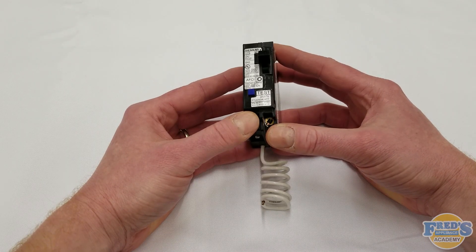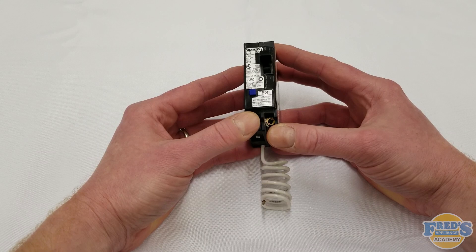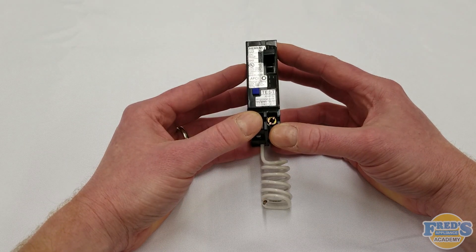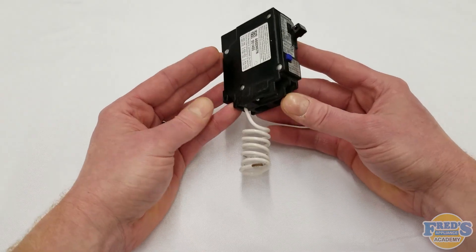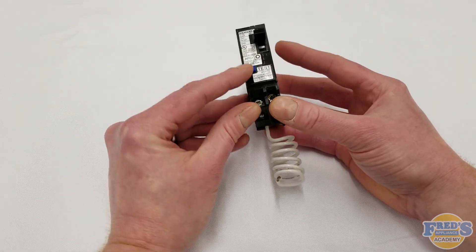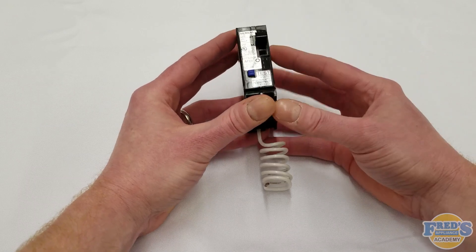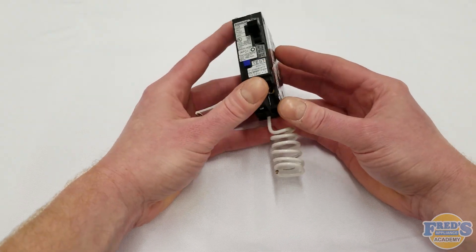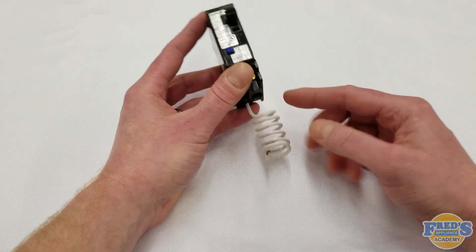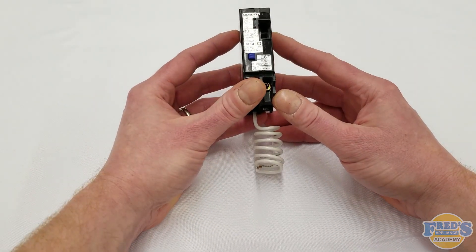Instead of having your actual outlet be the arc fault circuit interrupter, in a modern application the whole house is protected via the breaker. This is what the breaker would look like - it has a little test button right here as well as toggling on and off like any standard breaker. They also can be identified by having AFCI labeled on them and having a neutral wire attached to the breaker itself.